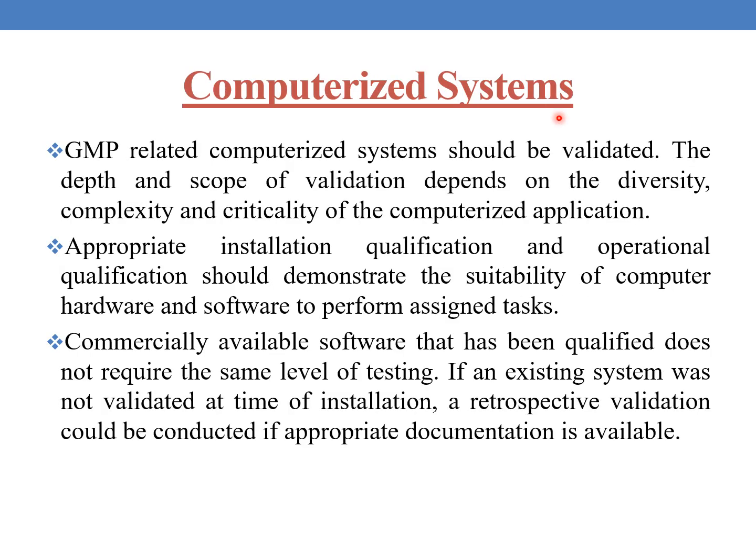Coming to computerized systems. Good manufacturing practices related computerized systems should be validated. The depth and scope of validation depends upon the diversity, complexity and criticality of the computerized application. Appropriate installation qualification and operational qualification should demonstrate the suitability of computer hardware and software to perform assigned tasks.